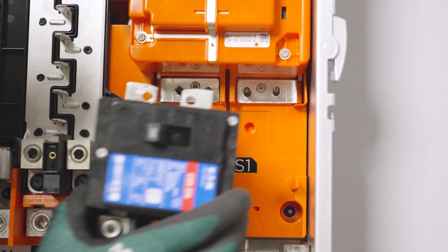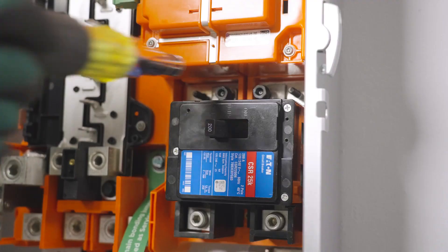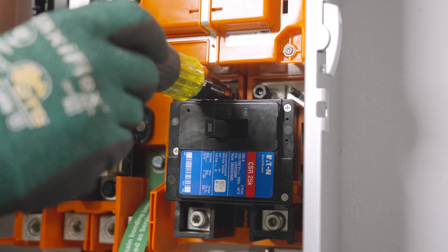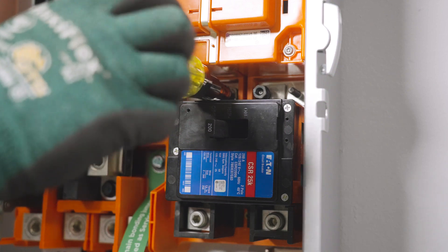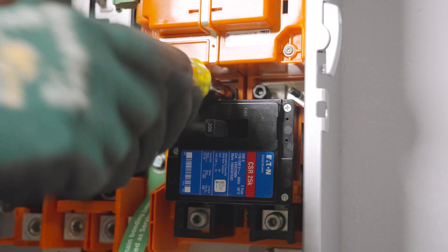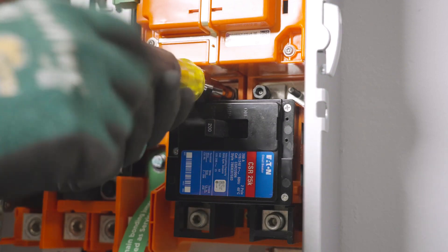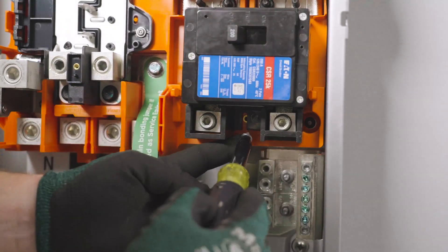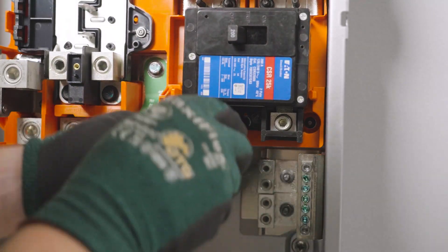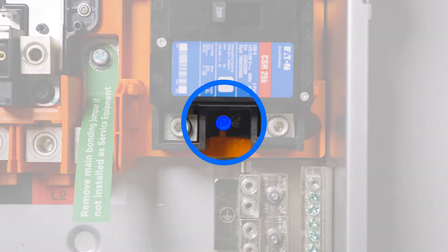Place the main breaker over the S1 and S2 posts and secure it with two nuts, torquing them to the specs listed inside of the equipment. Secure the bottom portion of the main breaker with the manufacturer-provided hold-down screw.